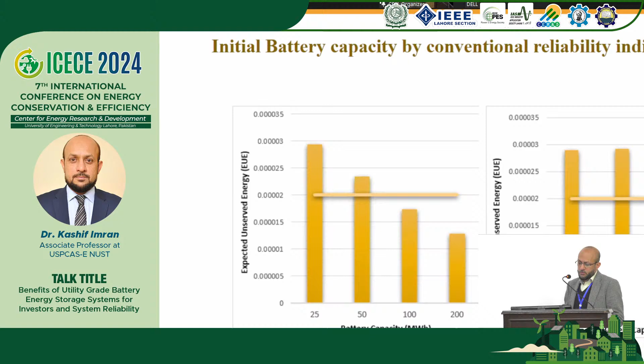for loss of load hours, again in this slide, we saw that when we go up to 100 megawatt hour battery, then we are able to meet the minimum threshold specified in the grid codes. So this is how it worked. We explored multiple indices. This is the next: loss of load expectation and loss of load probability. Loss of load probability is calculated on an hourly basis for 24 hours, because we were running the simulation for 24 hours.